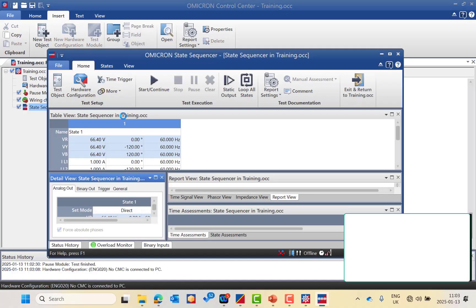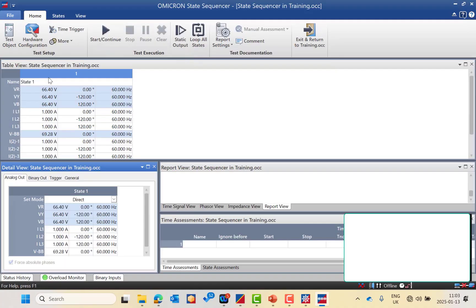The state sequencer allows you to create many states. You can simulate the pre-fault in the first state, then simulate the fault state, then post-fault state, then pre-fault again, then another fault — simulating different types of state sequences. It can be used for many applications, such as auto-reclosure, circuit breaker fail, switch-on-to-fault function, or simulating trip commands with zone 2, and many more.